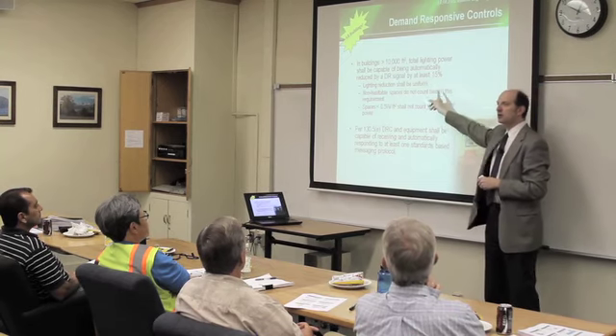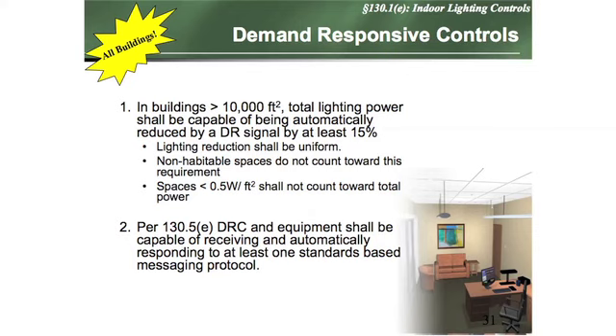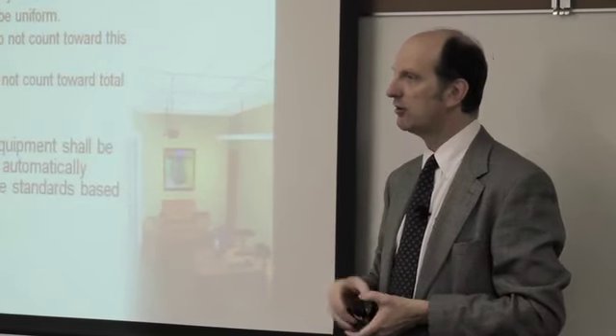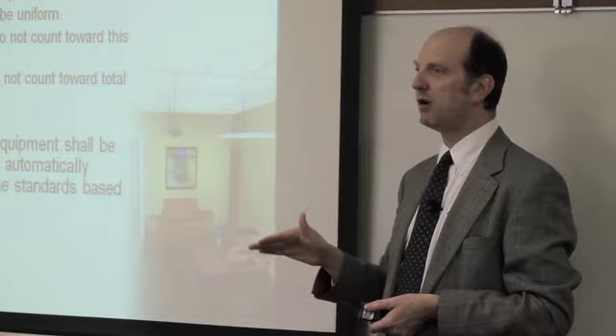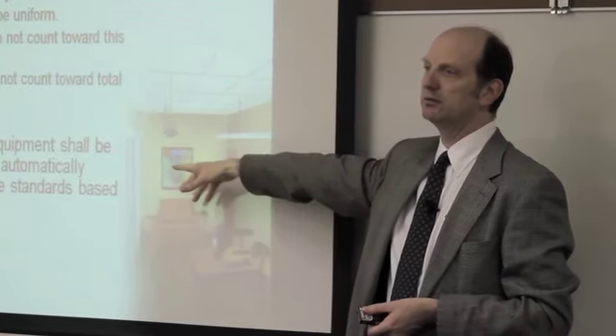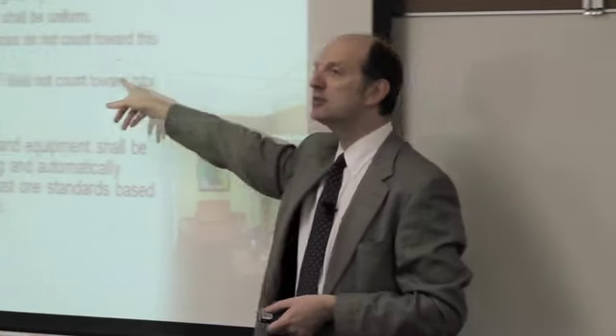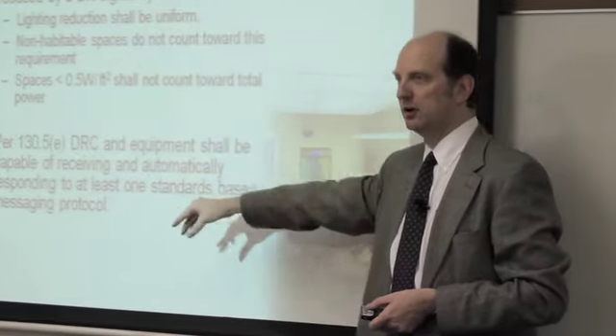And if you thought you'd just turn off all the closets, you can't do that. They say it's only habitable spaces. The give back is that anything that's less than 0.5 watts doesn't count toward the total power. If you get a space that's below 0.5, then you don't have to include that. So if my entire building is less than 0.5 watts per square foot, I don't have to worry about this at all. If I'm under 10,000 square feet, I don't have to worry about this at all.